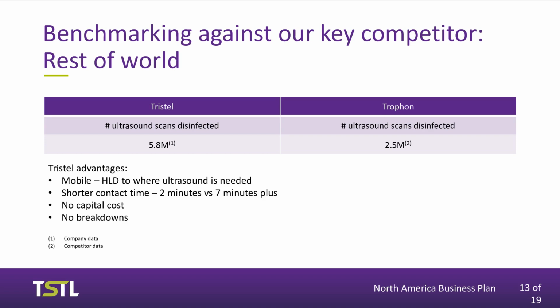And the advantages that our product has, once again, we're mobile, we can take high-level disinfection to where ultrasound is needed. But another great advantage is the efficacy of our chemistry. Our contact time, as approved by the FDA, is 2 minutes, and the Trophon machine requires 7 minutes of uninterrupted contact between the hydrogen peroxide and the probe before the probe can be taken out of the machine. Other disinfectants, the liquid soaks, can take as long as 20 minutes. Disinfection is a rate-limiting step for the number of patients that can be seen by an ultrasound probe or an endoscope. The quicker you can disinfect it and make it safe and available for use on the next patient, the more patients you can see in a clinic. So contact time for us is the holy grail.